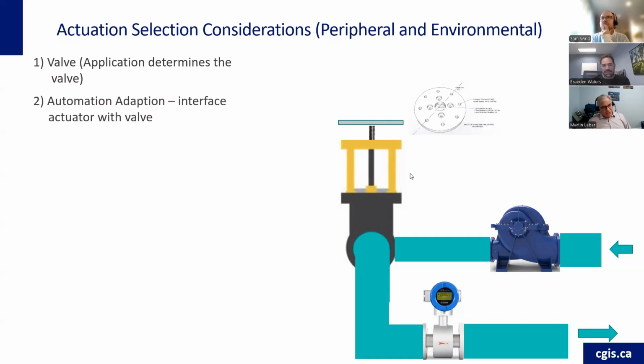In some applications where the bolt pattern of the actuator you choose does not fit the valve, you may have to incorporate an adapter plate. And there are considerations when you do that also, because there's added space used up by the adapter plate.